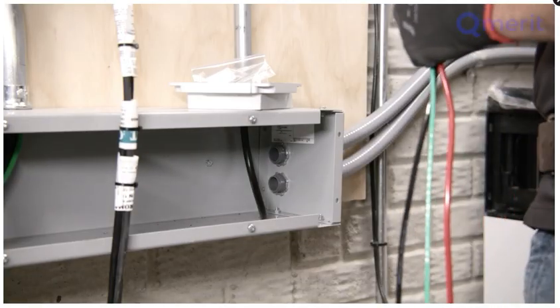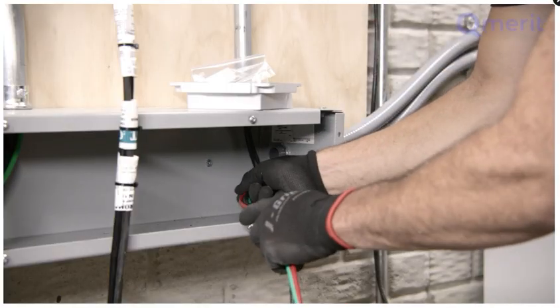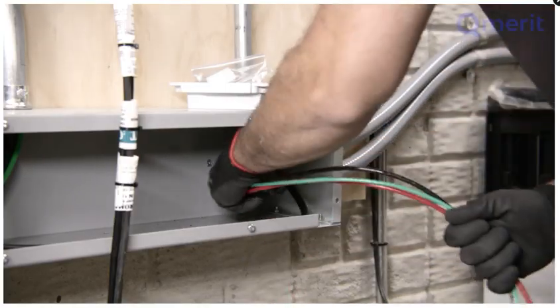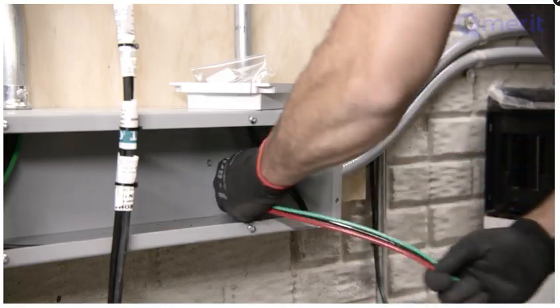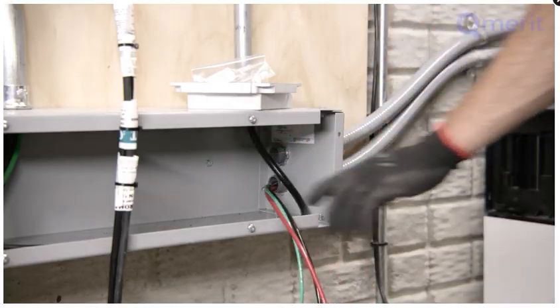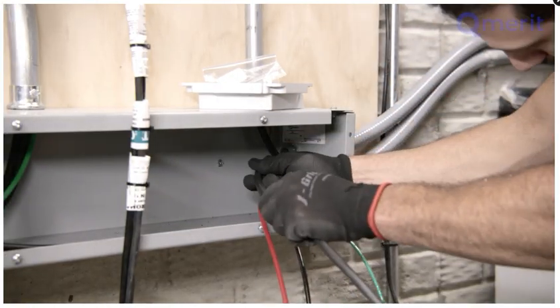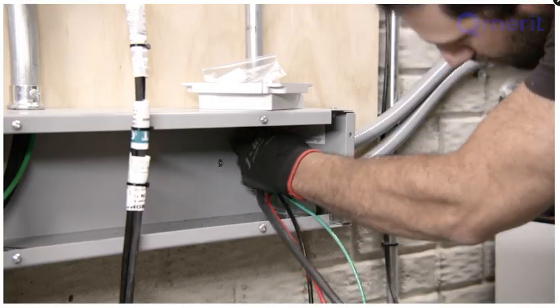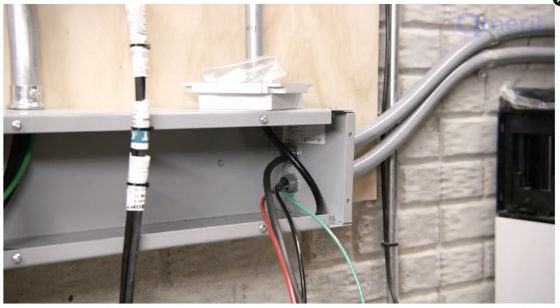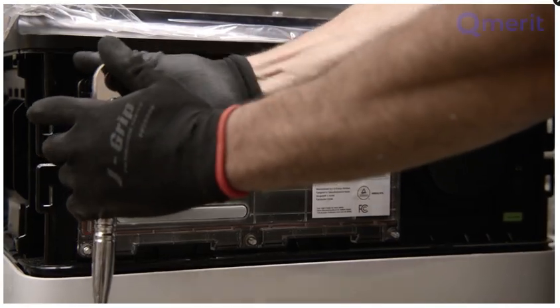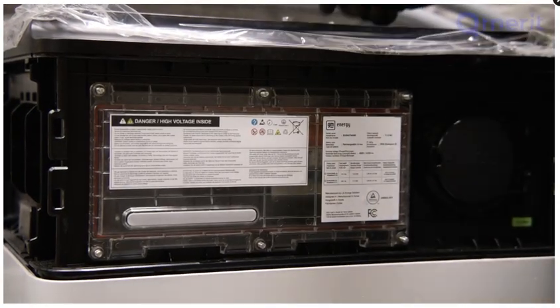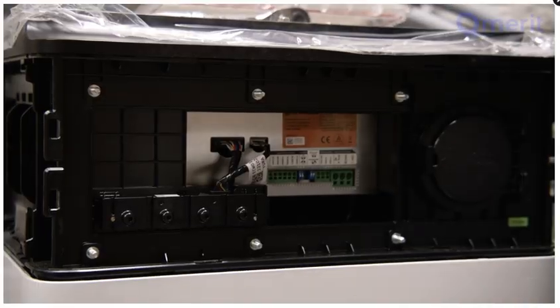After getting your conduit in place, you'll need to feed the wires through the conduit. Use 8 to 10 gauge copper wire and do not exceed a length of 35 feet. The communication cable needs to be between 18 and 22 gauge. Do not exceed a length of 35 feet as well. Remove the front cover on the BCU to access the termination points and the wire duct.